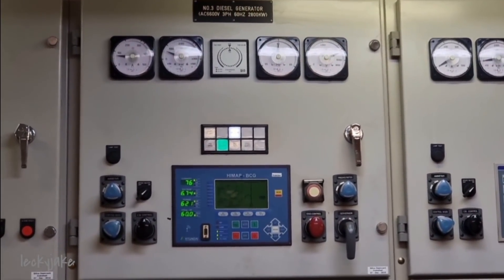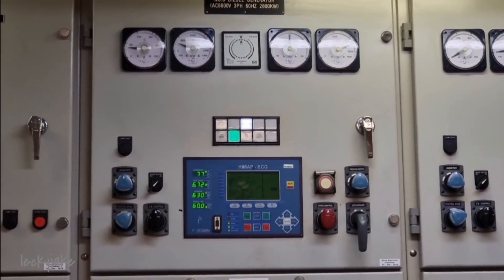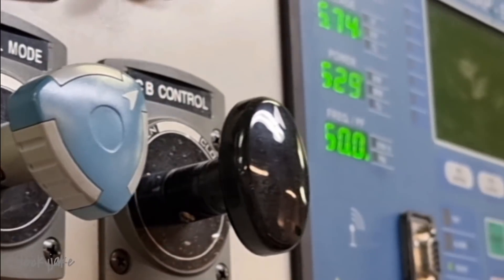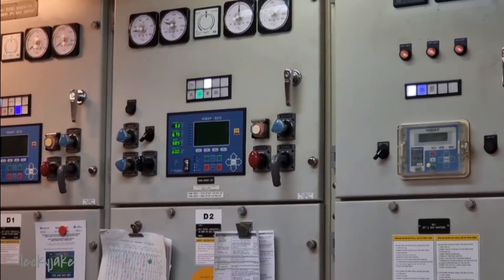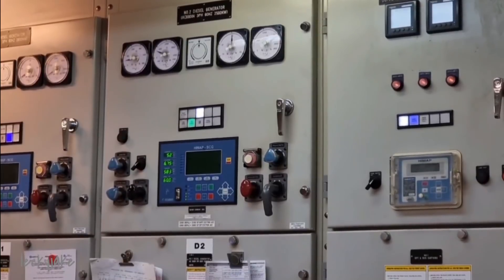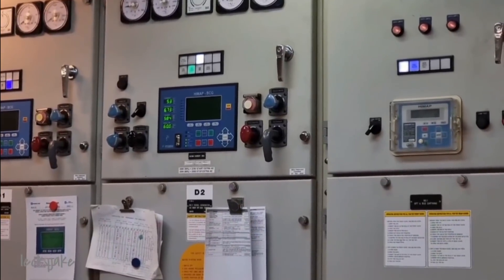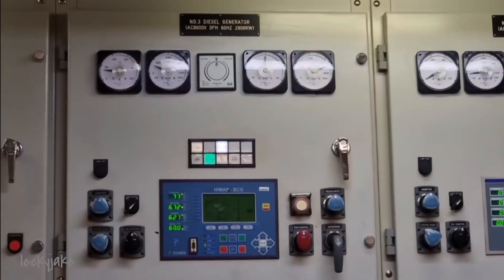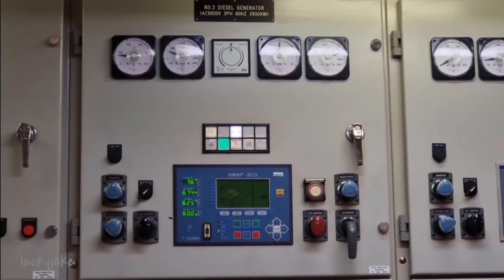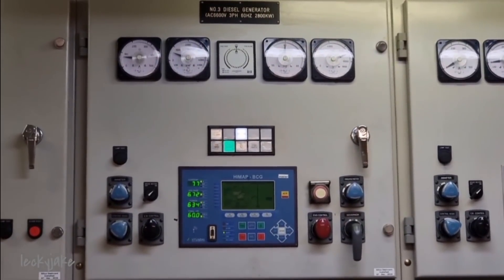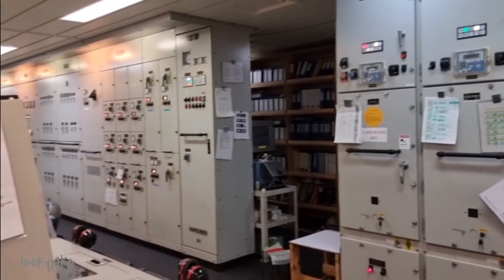The PMS automatically controls the diesel generators for efficient operation. Automatic starting, synchronizing and load sharing is provided for the ship's generator set. The system automatically equalizes the generator frequency with bus bar frequency and energizes the generator's VCB to connect the two circuits at the moment when the phases coincide. Automatic load sharing then ensures that each generator is equally loaded.